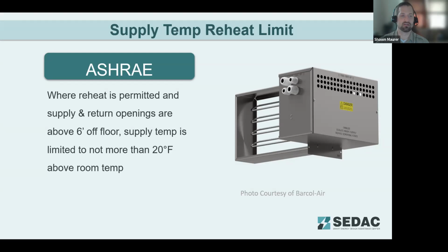So as we're noting here, if return openings and supply openings are greater than 6 feet above the floor, the supply temperature shouldn't be more than 20 degrees warmer than the room temperature. And again, it just prevents the potential for stratification where all the heat is trapped up by the ceiling and the actual occupied space of the room down near the floor isn't conditioned properly.